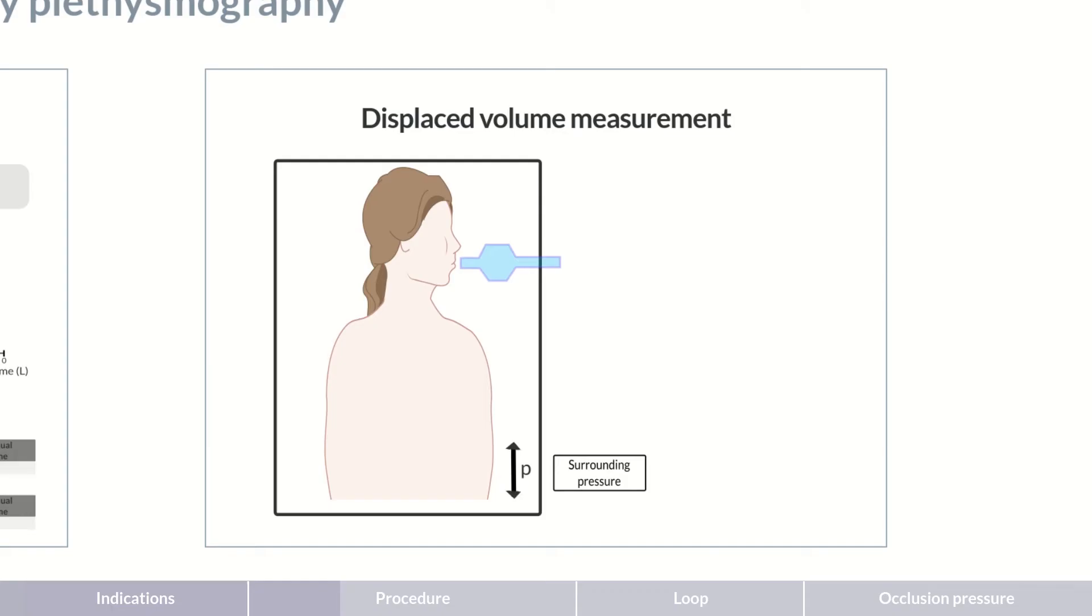A second pressure sensor is in the mouthpiece that can simultaneously measure pressure in the mouth and airflow. Let's first look at what the pressure sensor in the cabin measures.